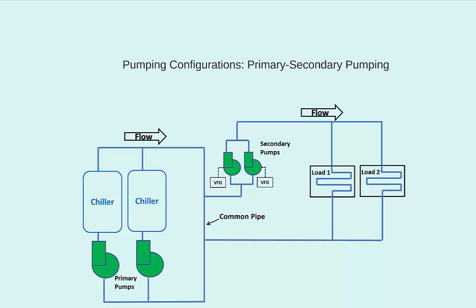If one of the primary pumps is operating at 100 GPM, and there is not that much load on the system and the secondary pumps are operating at a reduced speed and only pushing 75 GPM, then 25 GPM will be flowing downward in the common pipe as shown. If the building load increases and the secondary pumps start speeding up, there will come a time when all of the flow coming off of the chillers will be sent to the coils. In this instance, there will be no flow going through the common pipe.